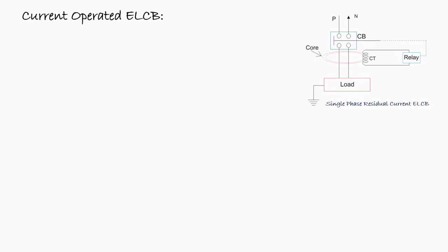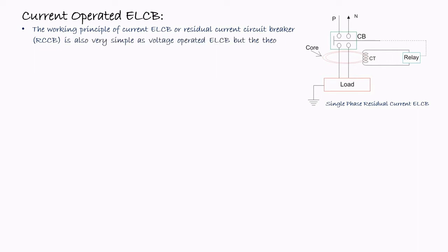Next is the current operated ELCB. So here the circuit diagram is shown. The working principle of the current controlled ELCB, or residual current circuit breaker, that is RCCB, is also very simple, as with the voltage operated ELCB. But the theory is entirely different, and the RCCB is more sensitive than the ELCB. Here we have to remember one thing. The current operated ELCB is also called the residual current circuit breaker or RCCB. It is more popular by the name RCCB.